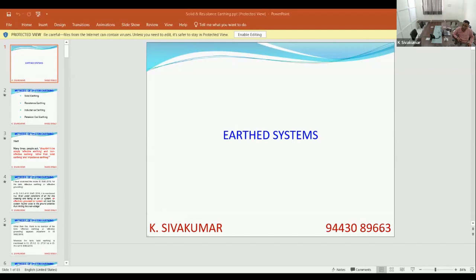Generally in any industry, the positive sequence reactance will be very high compared to the resistance part. So in solid earthing, the ratio of R0, the zero sequence resistance or the resistance of the earth fault path, to X1 should always be less than 1. So you know your X1, you measure your R0, or earth fault loop impedance, as they call it nowadays, and compare with X1. If the R0 by X1 ratio is less than 1, your system is solidly grounded.